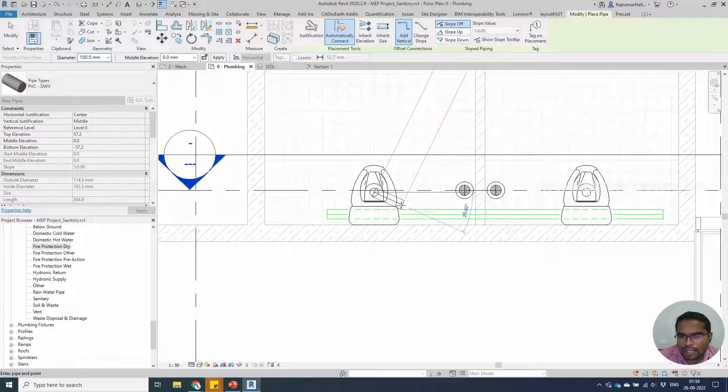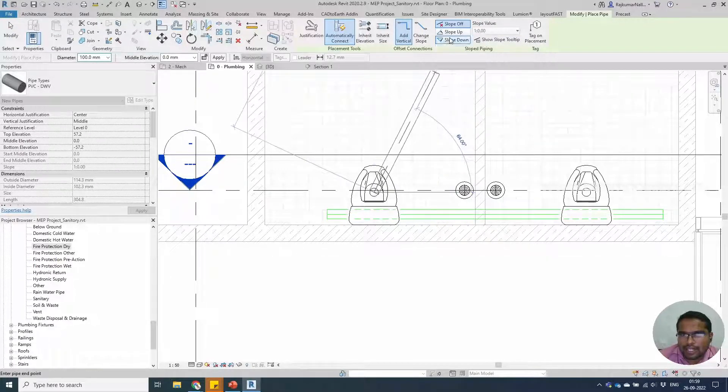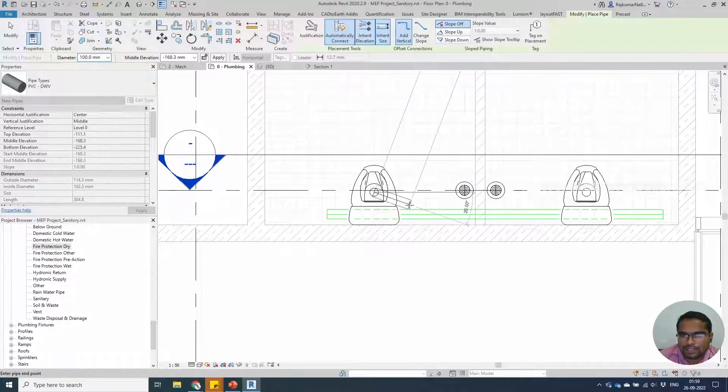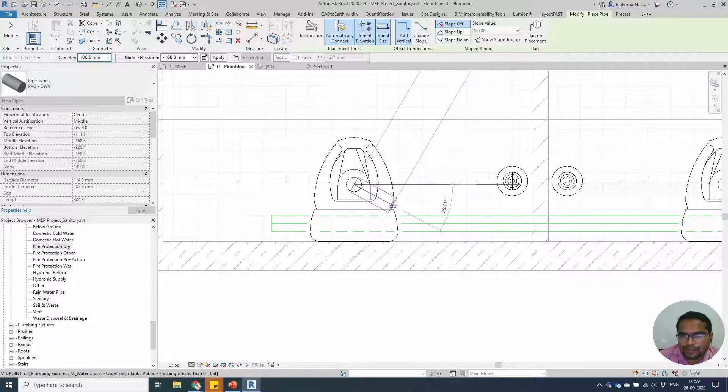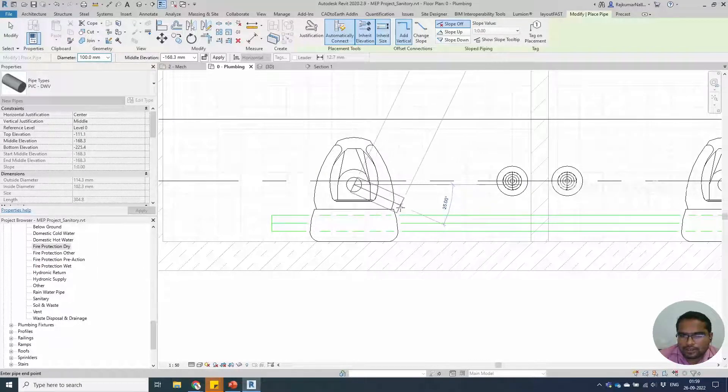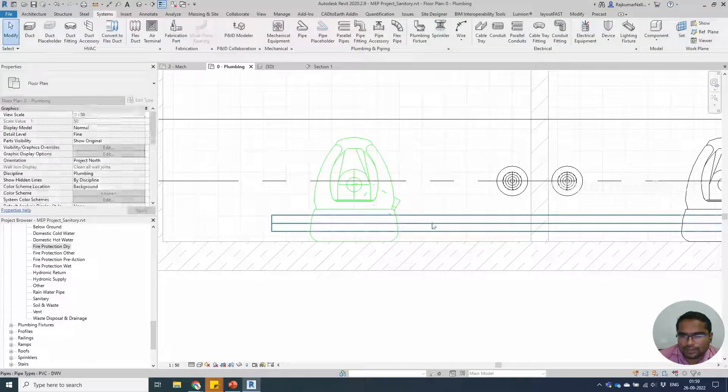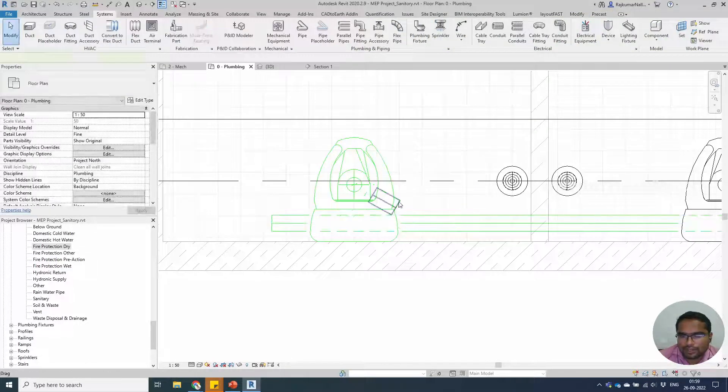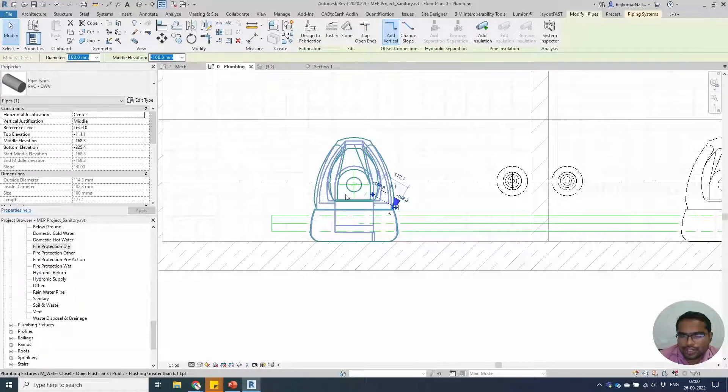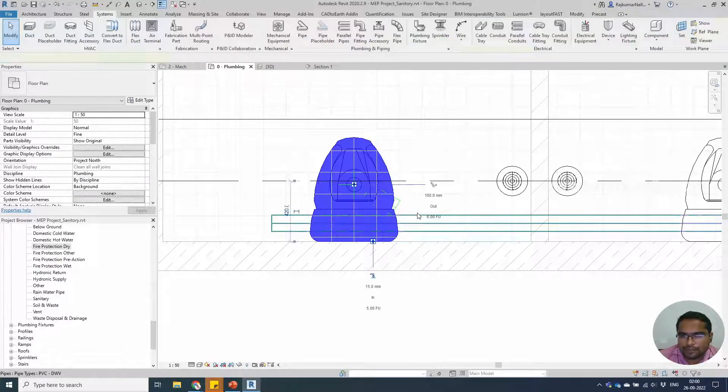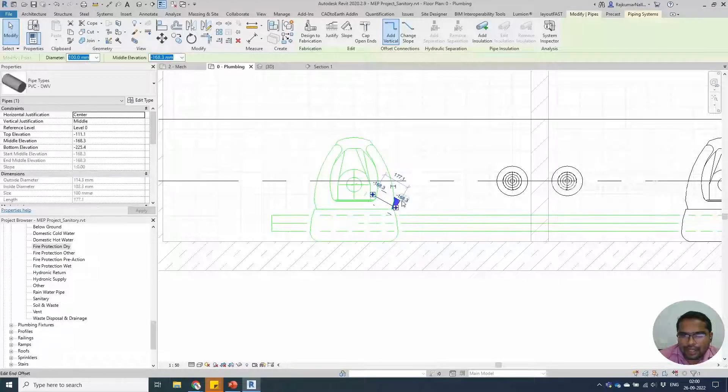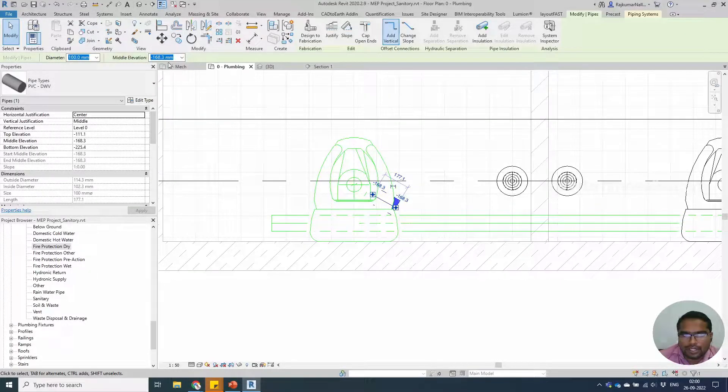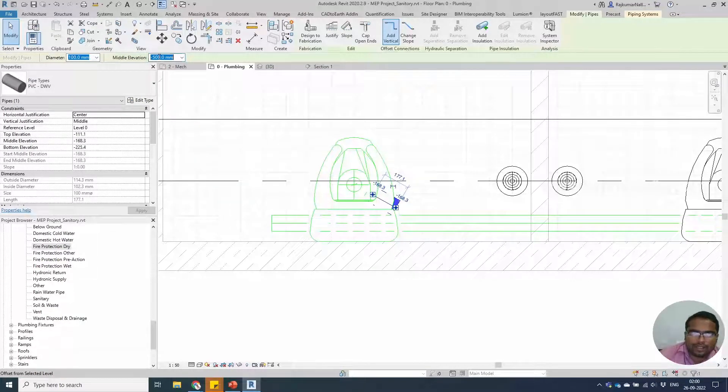This time, I am going to use inherit elevation, inherit size. I will draw it at 30 degrees like this. The picture got changed into a green color, which means we are connecting to the sanitary. If I check the pipe height for drawing, you will see that this is at minus 168. We need minus 500.